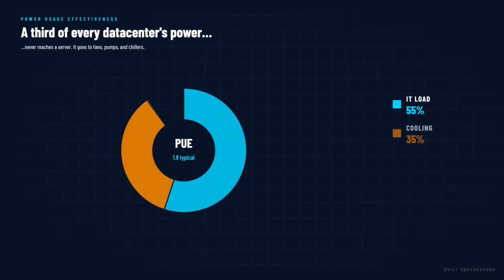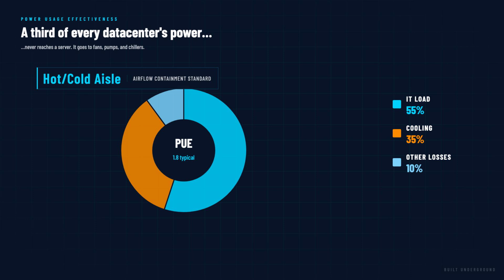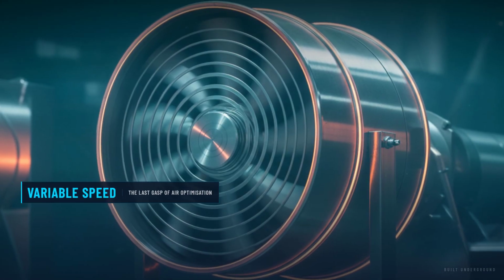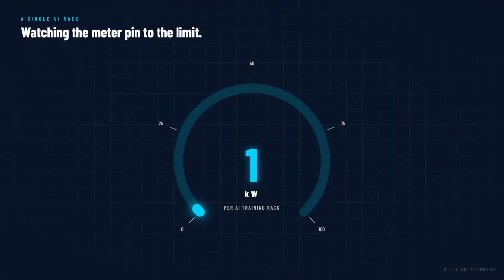For years, the industry optimized around these limitations. Hot aisle and cold aisle containment reduced mixing, variable speed fans improved efficiency, higher supply air temperatures reduced chiller load. These incremental improvements kept air cooling viable through the cloud computing era. Then AI changed the equation overnight.